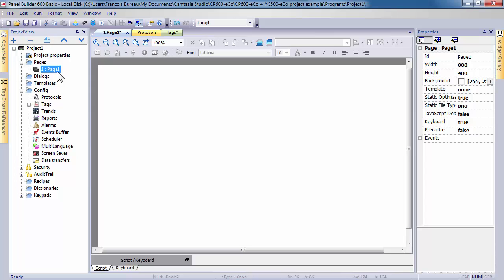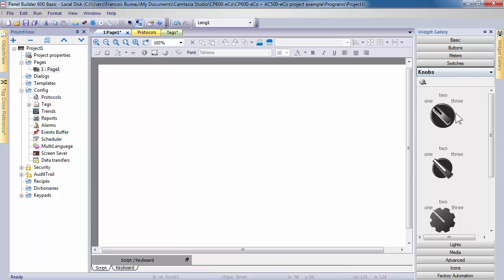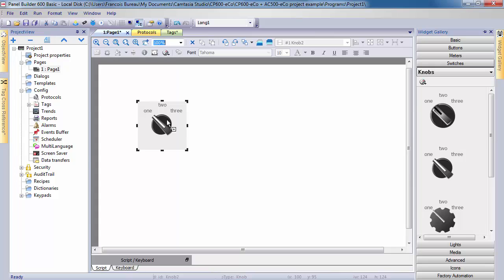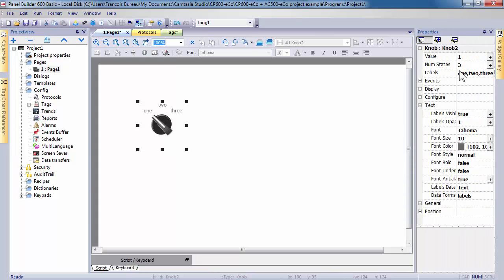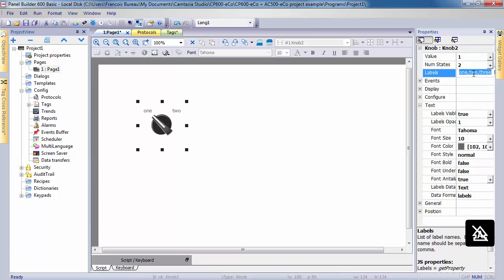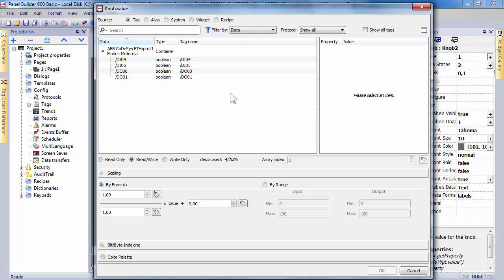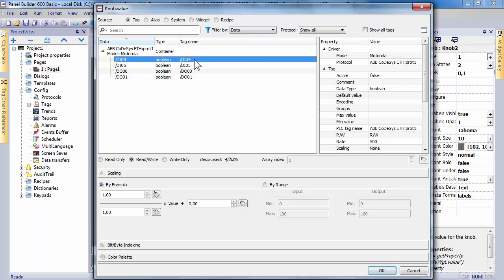We are going to use some basic widgets to demonstrate and simulate an HMI application. For instance, we can start by choosing a knob in the list of widgets, then by the drag and drop action, you position it on the page editor. As soon as the widget is on the page, the object properties appear on the right side, and they are accessible for configuration. For configuration, the default properties could be changed or used like they are. To change a property value dynamically, you can attach them to tags or variables, just by clicking plus on the property line, and using the action attach to. Then when the tags editor is open, you can see and select the AC500 eCo DI04 digital input previously imported to animate your widget. And if necessary, adapt its configuration, especially pay particular attention to read-write option associated to your tag.